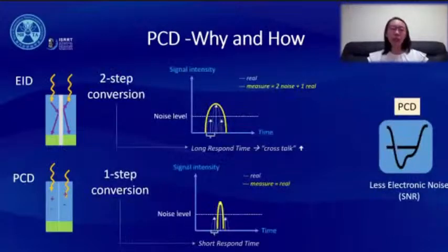In traditional EID, the two-step conversion requires longer response time for signal detection. Pulses under the noise level are read and mixed together with the real signal because of crosstalk. Therefore, finally, the image quality is degraded. But for the PCD, which is one-step conversion, the image shown in the lower part of this PPT, the short response time helps the system to clarify the noise and exclude it from the real signal. Therefore, the noise can be eliminated.